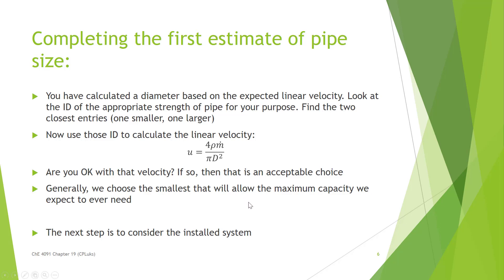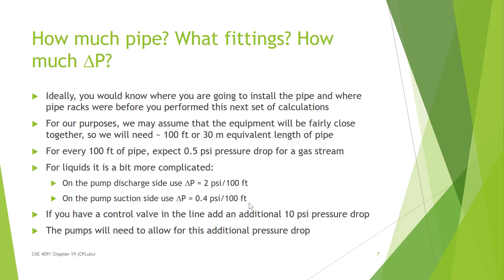Now we want to look at our installed system. We need to think about how much pipe we'll need, what fittings, and what the pressure drop across the system will be. Ideally you know where the two pieces of equipment are that you're connecting, where the pipe rack is, and whether you need to go up over a road or can go straight across. You add up the length of pipe and the equivalent length for all fittings to determine an equivalent total length. For our purposes, we'll assume equipment is fairly closely placed and say we need 100 feet of pipe — that's the equivalent length including all fittings.